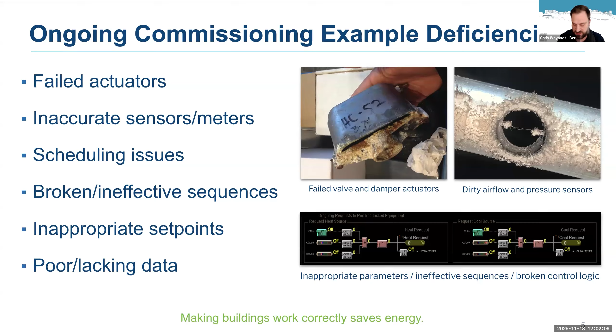We also regularly update the sequence of operations for the control systems in our buildings. We use SkySpark to identify when we have set points on our HVAC systems that are inappropriate, either overcooling or overheating spaces. And we spend a lot of time addressing poor or missing data, especially with utility meters.